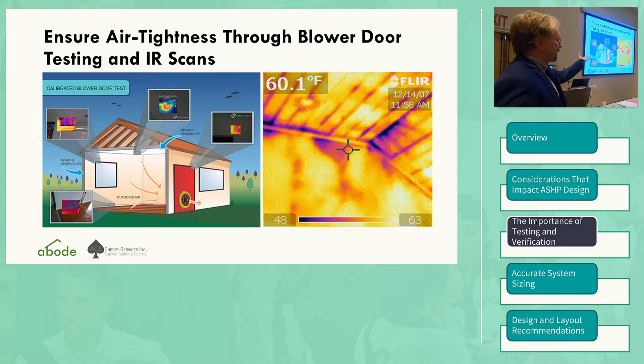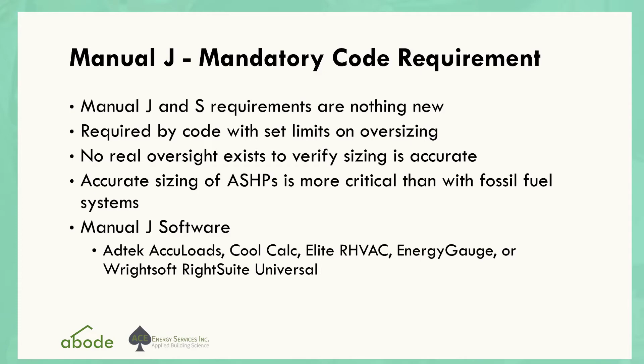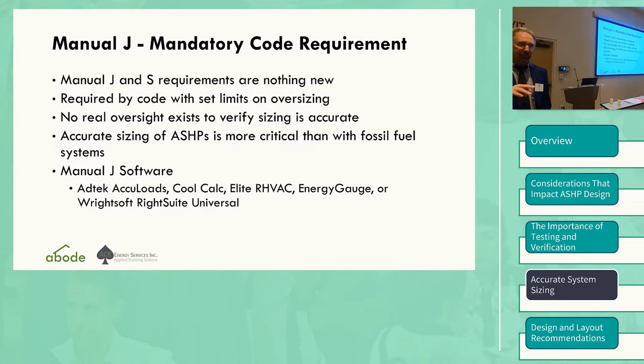Accurate system sizing for new construction - Manual J and S requirements aren't new, they're a code requirement. Code sets limits on oversizing, 40% above, so the equipment you put in isn't supposed to be more than 40% above the Manual J, for heating and cooling. However, if you're in a Mass Save program, and all our builders are because they want the rebates, you have to be within 15% of the design load with the equipment you put in. So that's good to know.